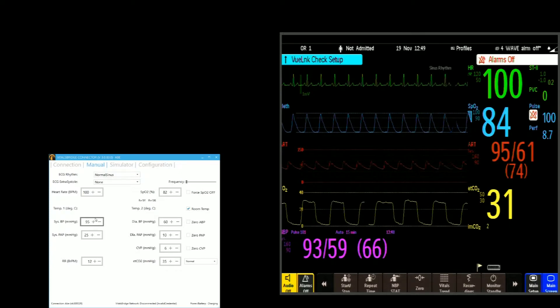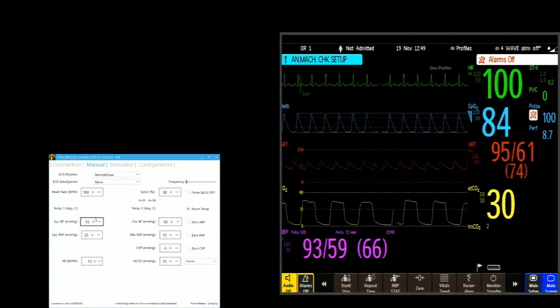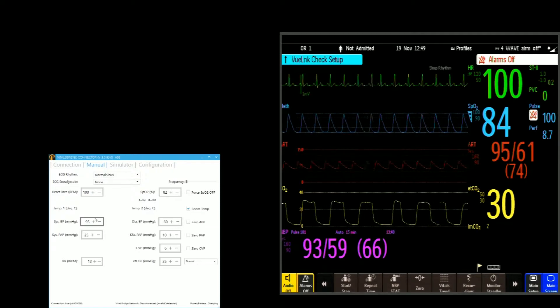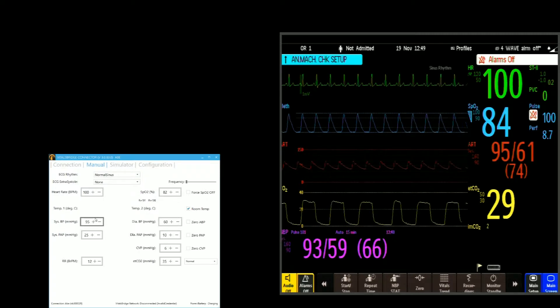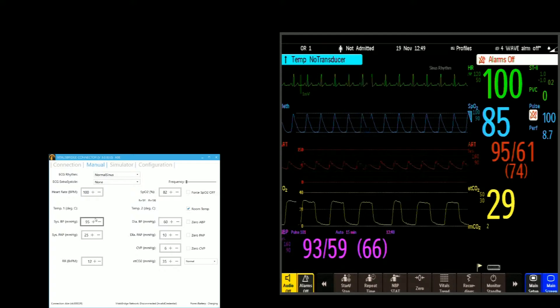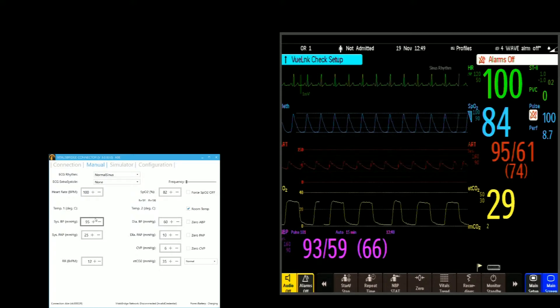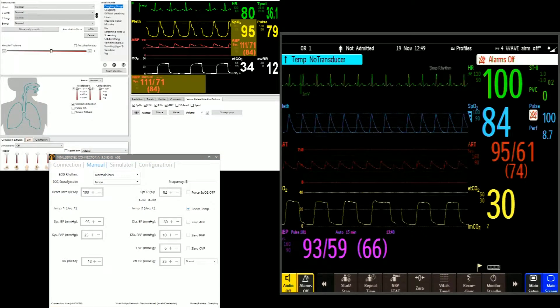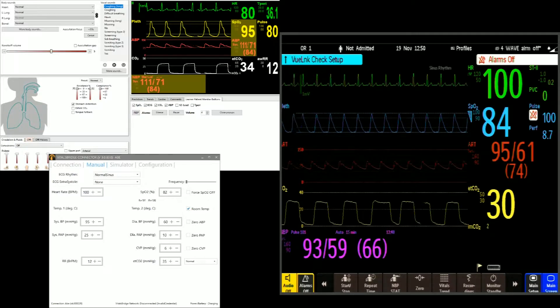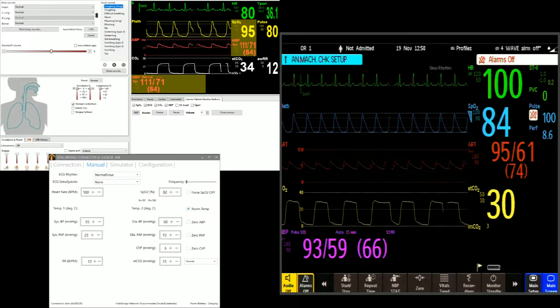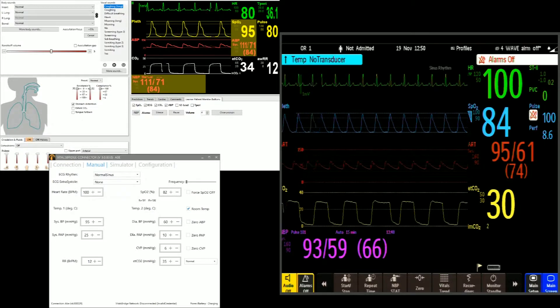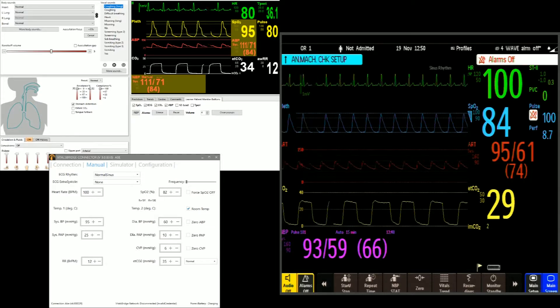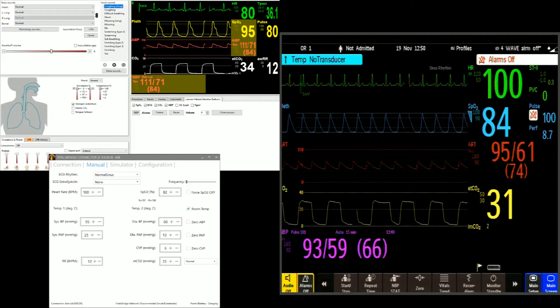It's a great way to get set up and check your vital signs. It's also a great way if you're using a low-fidelity simulation or a standardized patient — you can use this interface to control the vital signs and get what is desired onto the real patient monitor. Now let's bring up the LLEAP software and show the second way you can communicate with your mannequins. Those who use Laerdal simulators are probably very familiar with this interface used to control the mannequin's vital signs. The nice thing is you can take an interface you're already familiar with, make changes using that instructor app, and have those changes reflected on a real patient monitor.